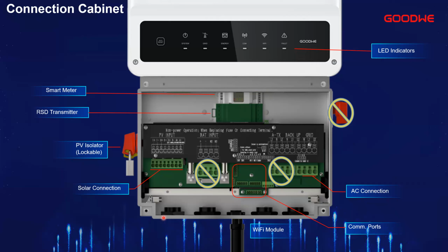Since we're doing string level optimization, we don't do module level monitoring, which is something that's often sold at the quote, at the street level, at the homeowner level, as a great feature. Of course, it's required if you're selling optimizers or microinverters—you have to do that, otherwise you can't see what your device is doing. You need some sort of peek into it. As much as people call it module level monitoring, it's really device monitoring: the optimizer or microinverter itself. We happen to be connected to a module, so we can also report on that, but that's really what it's doing. Since we don't have any devices at that level, we just report at the string level what's going on. So if module level monitoring is a requirement, this solution isn't going to get you that, at least not at this point. We may down the road provide a rapid shutdown solution that has monitoring in it, but not right now.